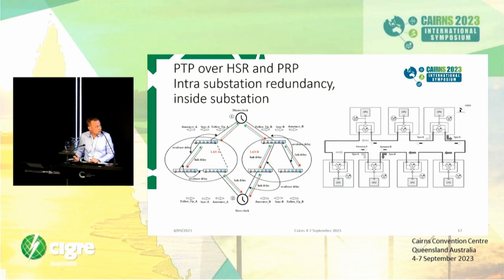High-speed switching redundancy and parallel redundancy protocol inside the substation. This is quite popular for building redundancy, using either a ring-style high-speed switching ring or parallel redundancy, which means sending everything in two directions.